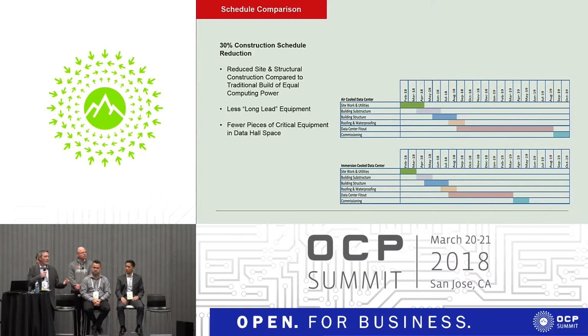The savings come in the actual fit-out of the data hall. We don't have a raised floor, no ceiling, we don't have a lot of demising walls, and I don't have a lot of complicated equipment to move in and out. We build a box, bring in the tanks, hook up piping to them, get the coolers operating, move in electrical systems, and there's a gigantic savings in commissioning cost. I don't have switchgear to commission, I have tanks to commission, and they can be factory tested.